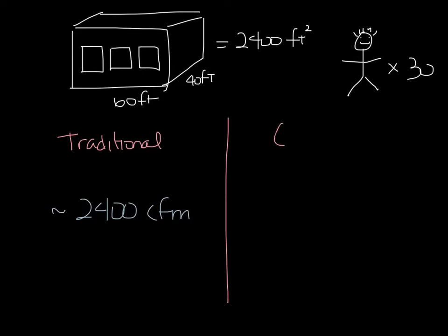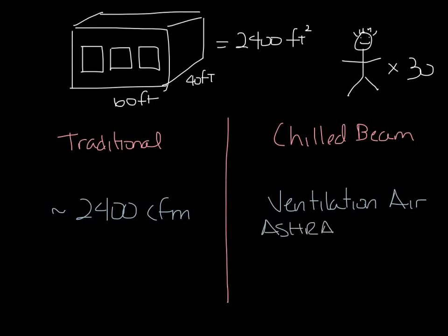If you have a chilled beam system, you would at minimum have enough airflow to handle the ASHRAE 62.1 ventilation rate.